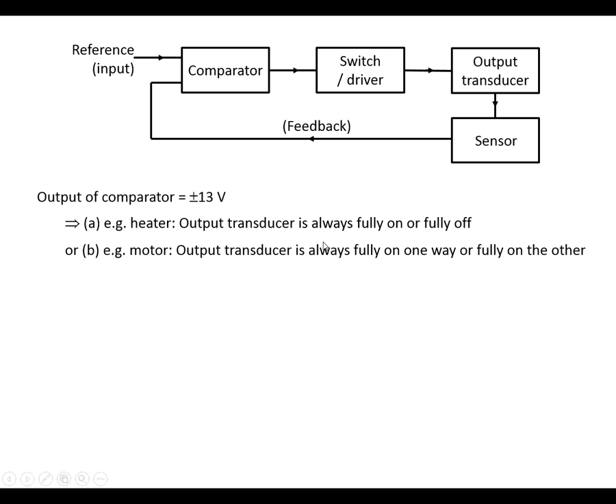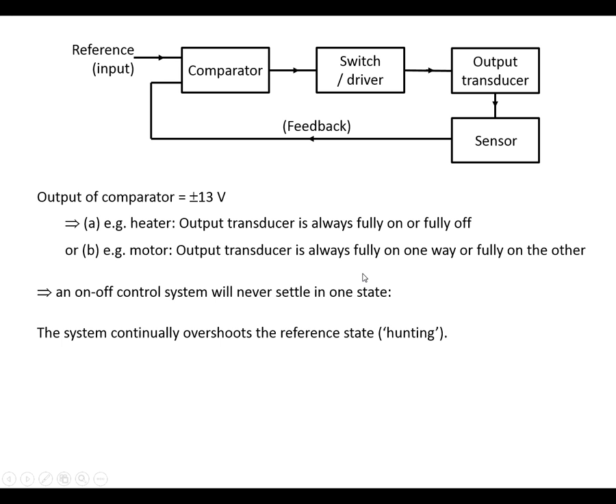Now because we've always got the system being fully on or fully off, or fully one way, fully the other way, it means that even when we're close to the desired conditions, we're still running at full power, which means it's never going to settle in one state because it's going to be overshooting where we want to be. And this is known as hunting.